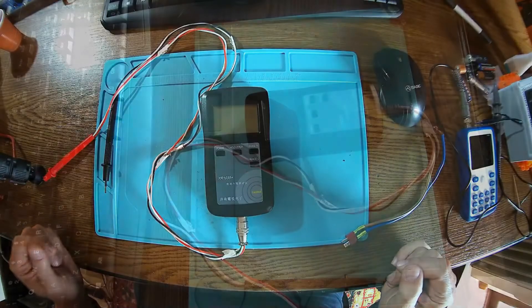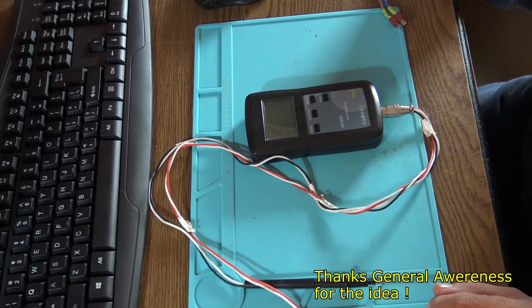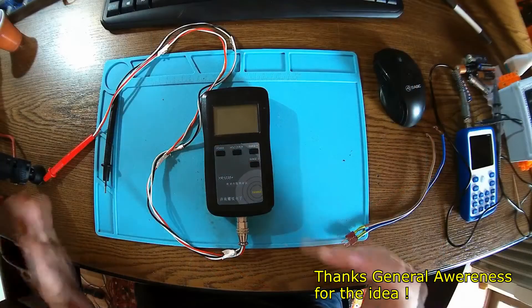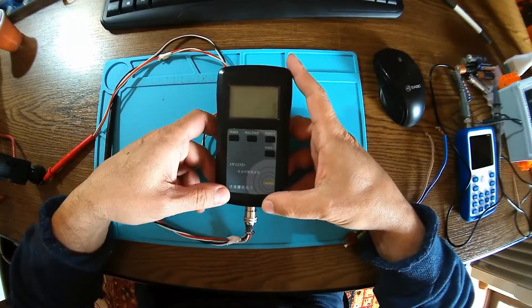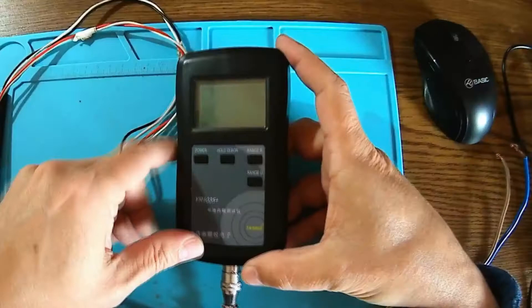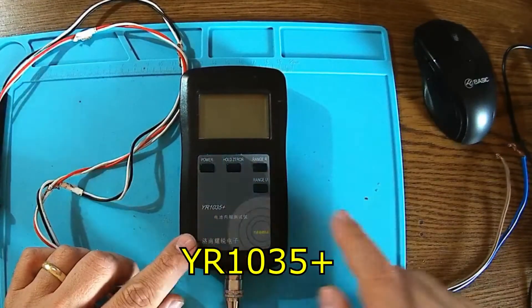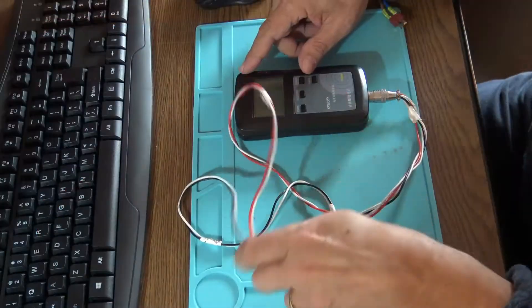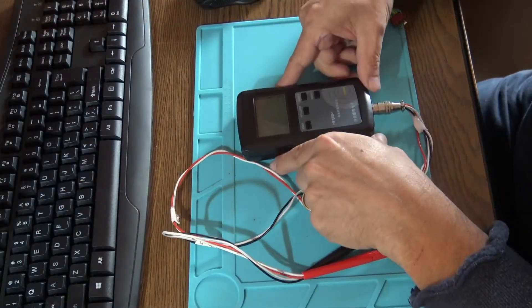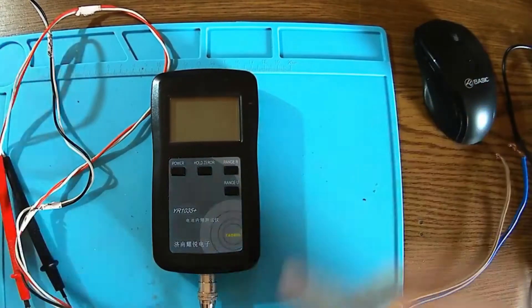Hello again — a new day, a new experiment. I've been asked by my subscribers for a better presentation of this measurement instrument, the YR1035+. This is a low impedance and low resistance meter, and it can also be used for measuring the internal resistance of batteries.